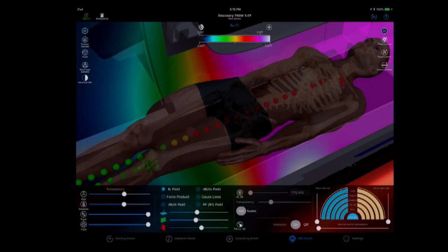The pacemaker is labeled, isn't it? And so this is just giving you a 3D spatial distribution. At this location in space, it's green. That means that you're nowhere near the threshold for which it's been labeled to be safely scannable. Yellow means you're approaching a threshold. Red, well, red means you've already passed it.